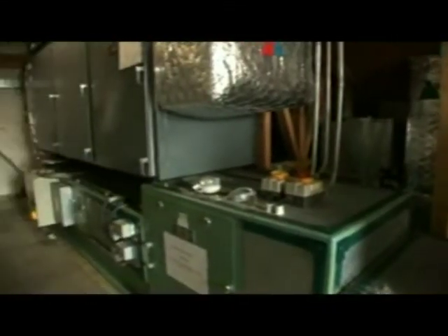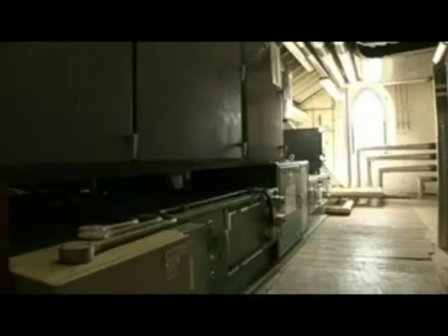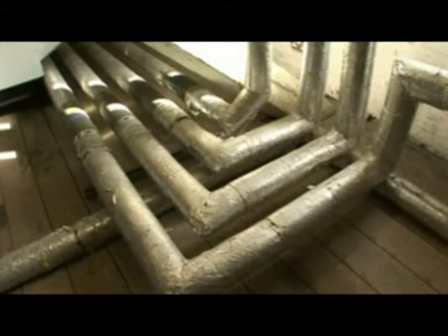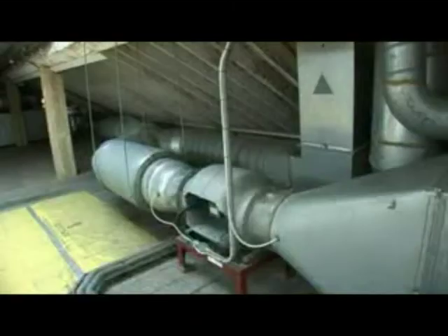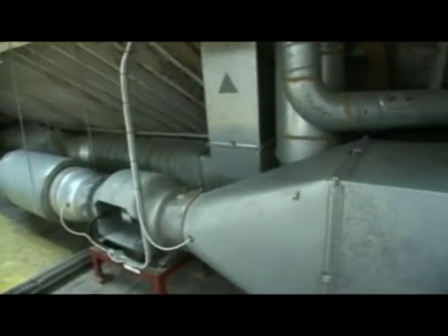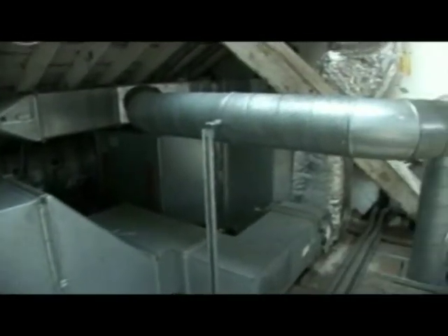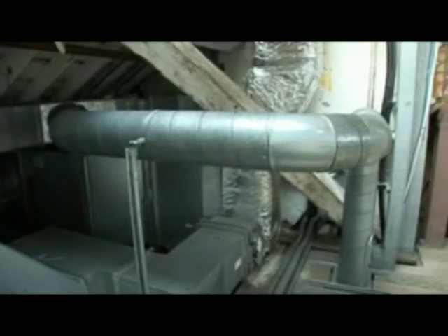Most of the basic items, such as insulating ductwork, setting up the correct deadbands on the AHU systems, reviewing the operating times and installing some solar reflective film to limit heat gain, were carried out within the first 3 or 4 weeks. Some of the recommendations are going to require funding, such as replacement of fans and motors, and these will be fed into the budget round for the following year.